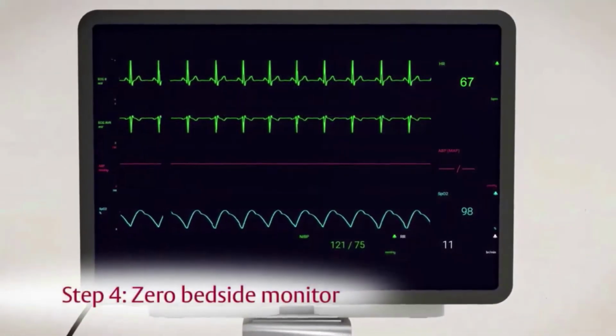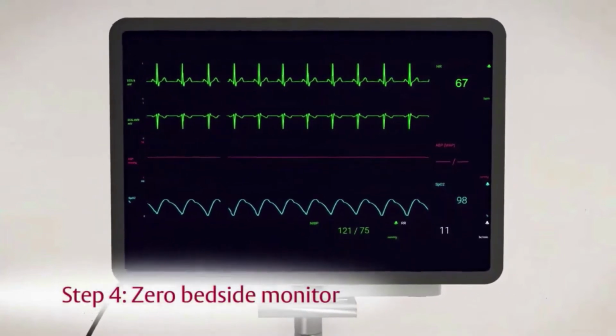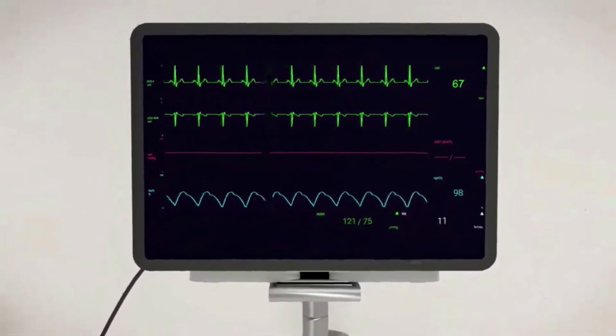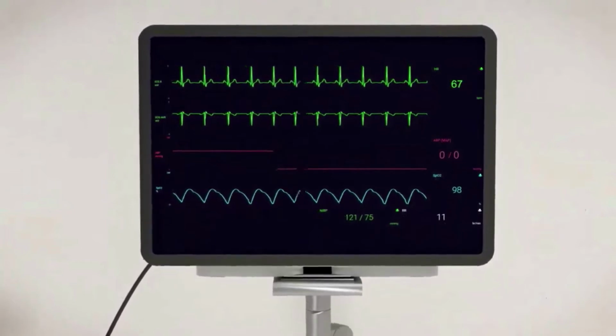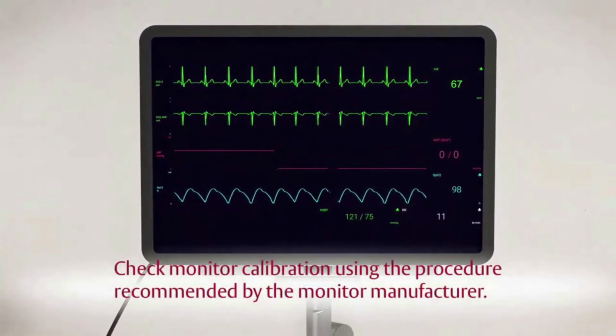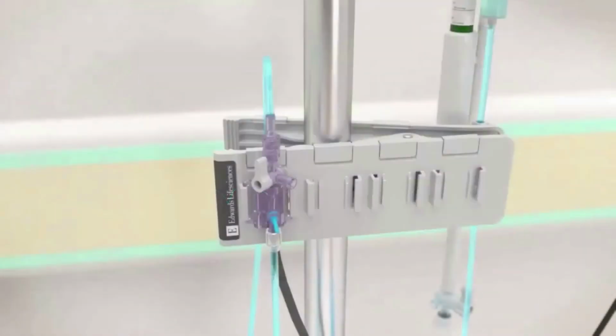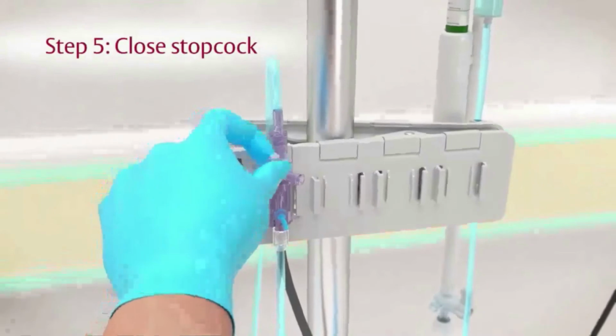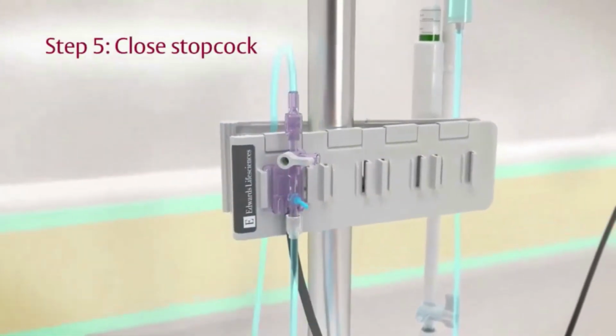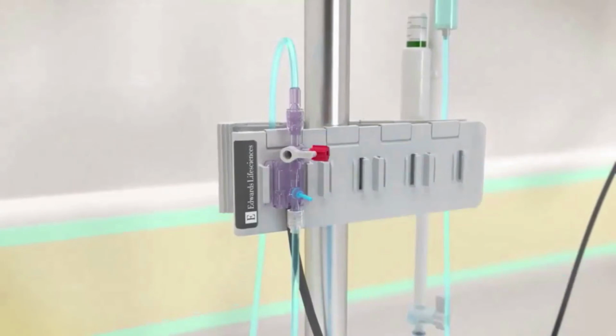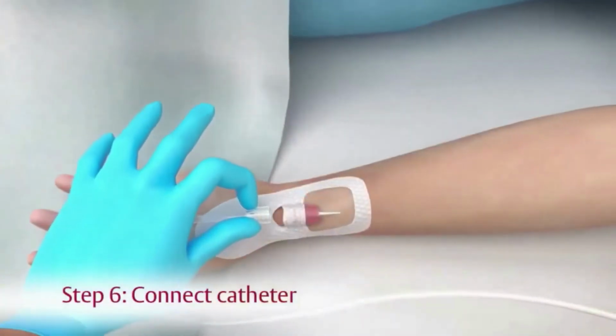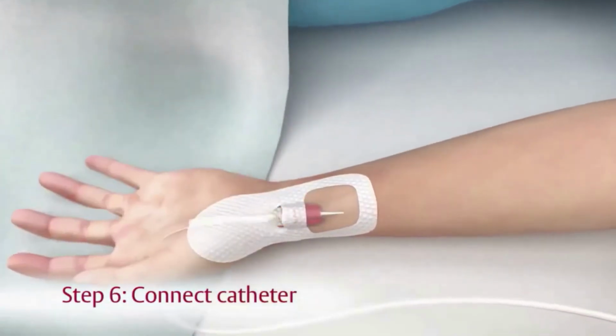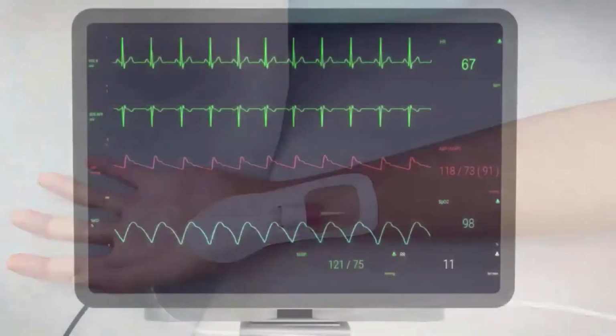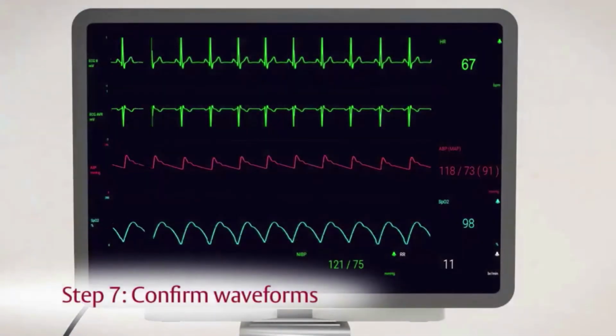Step 4. Select the zero function on the bedside monitor and confirm that the monitor's pressure channel waveform and numeric value display 0. Check monitor calibration using the procedure recommended by the monitor manufacturer. Step 5. Close the stopcock on the TrueWave transducer toward the vent port and then return the non-vented cap. Step 6. If not already connected, connect the TrueWave's pressure tubing to the patient's catheter. Step 7. Confirm the appropriate pressure waveform and numeric values are present.